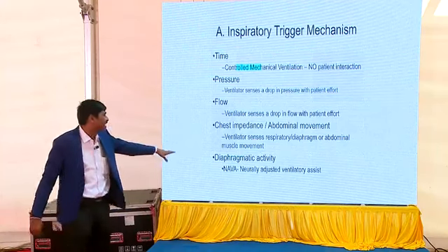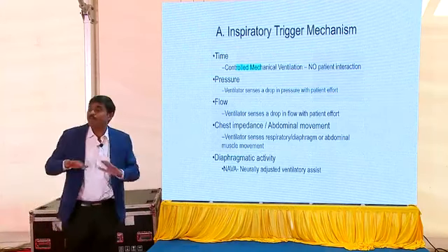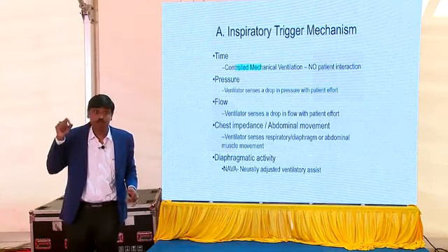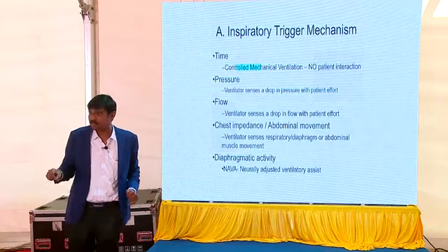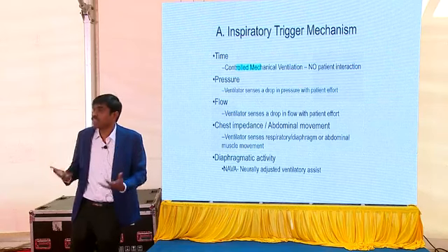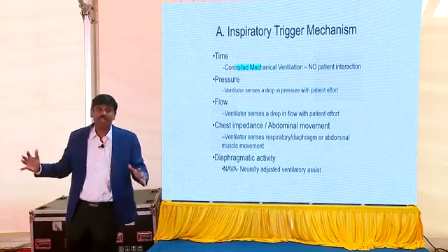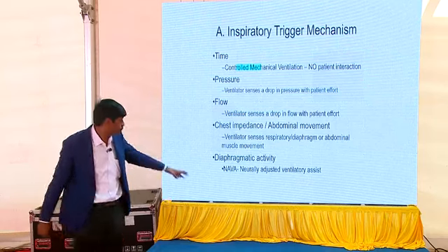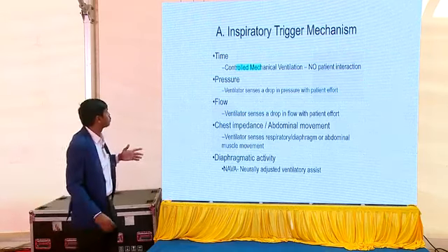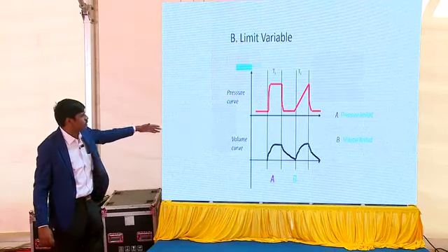Coming back, what this basically does is, the diaphragm is there, and you place a sensor near the diaphragm. It's going to pick up the electrical activity of the diaphragm itself. So in fact, that would be the earliest and the most sensitive trigger. You know the baby is going to breathe, and immediately you deliver. So that's how NAVA works, neurally adjusted ventilatory assist.